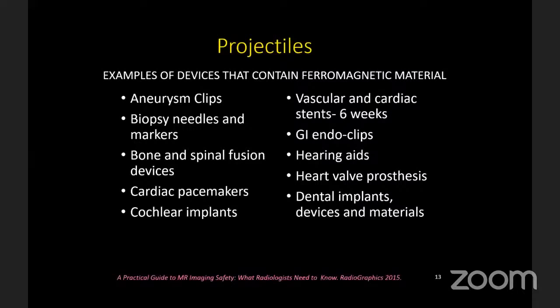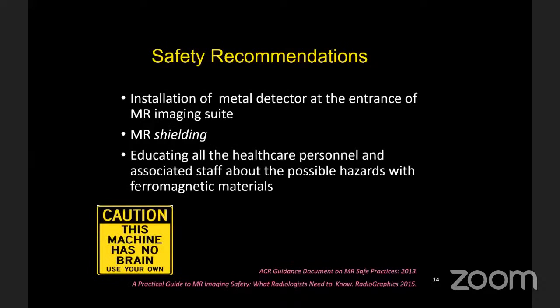Various devices or implants can cause projectile injury, including aneurysmal clips, spinal fusion devices, cardiac pacemakers, cochlear implants, hearing aids, heart valve prostheses, dental implants, and vascular stents placed before six weeks. Safety recommendations include installation of a metallic detector at the entrance of the MR suite, MR shielding, and educating all healthcare personnel about possible hazards with ferromagnetic materials.